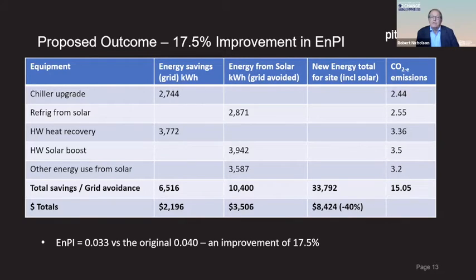Hot water saving from heat recovery reduces grid consumption by 21% of hot water use. That's purely a productivity measure because we're capturing heat from energy that's already been expended into the refrigeration system. The solar PV replaces grid energy for both the chilled water tank and the hot water boost.